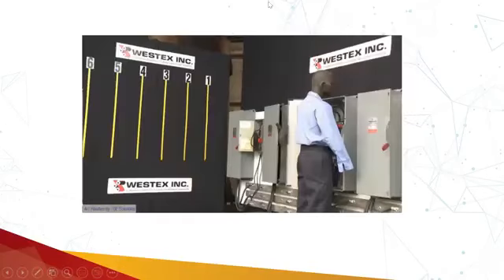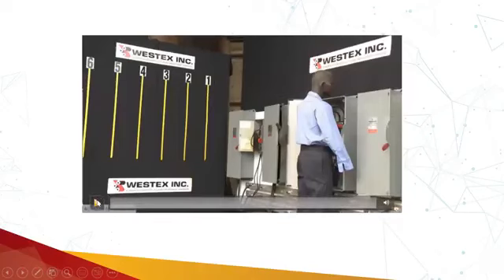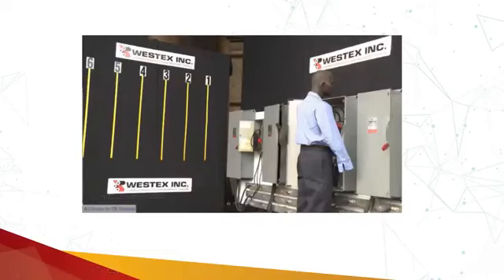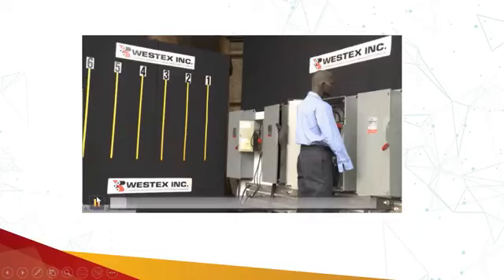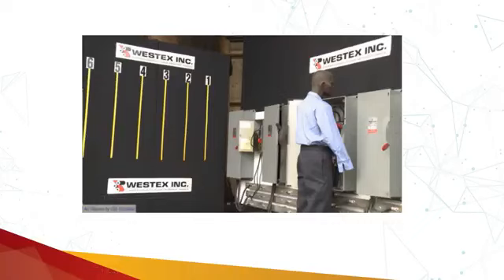Okay, let's move and see what is basically the arc flash burn and what is thermal burn. This mannequin is wearing polyester cotton shirt and pants. So this person is wearing only polyester cotton shirt and pants. He's not wearing arc rated clothing, and he's working on some low voltage system, LV system, which is operating at 400 volts. We're targeting category 2 here. So the category 2 term is being used.